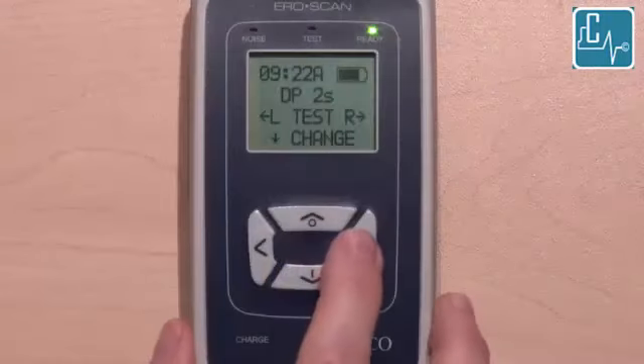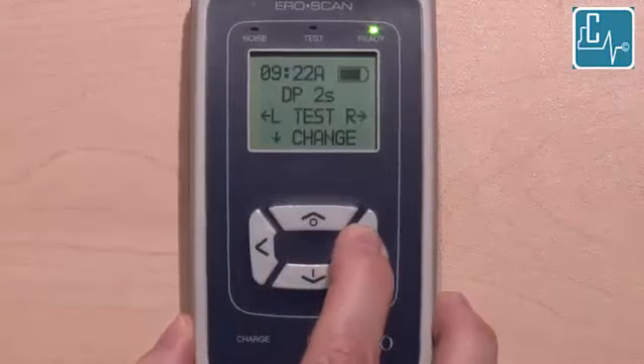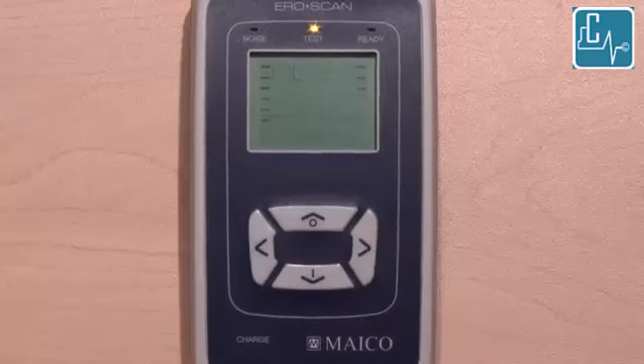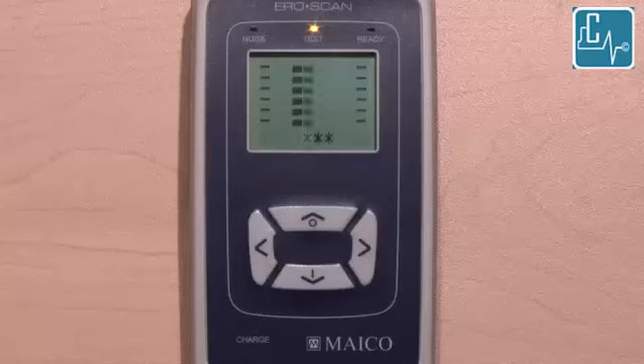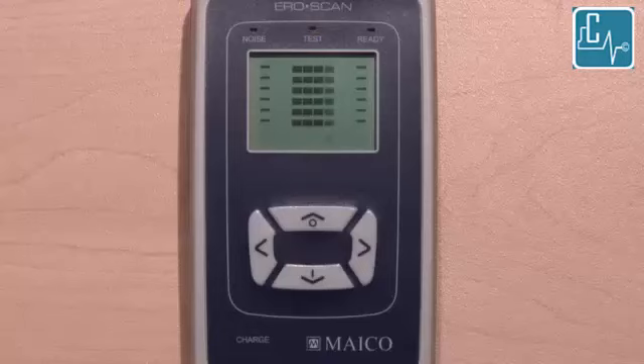To test a child with PE tubes in place, press and hold the left or right arrow for 3 seconds upon initiating the test. This will bypass the Auto Start Probe Check feature and go directly to the OAE test. This feature should only be used on children or adults with known PE tubes in place.